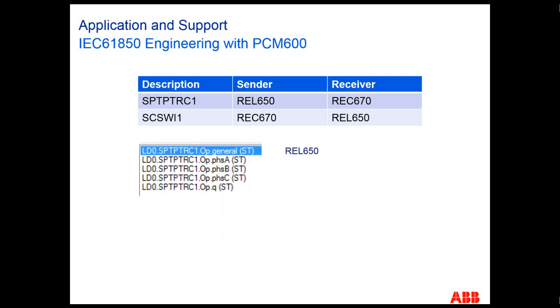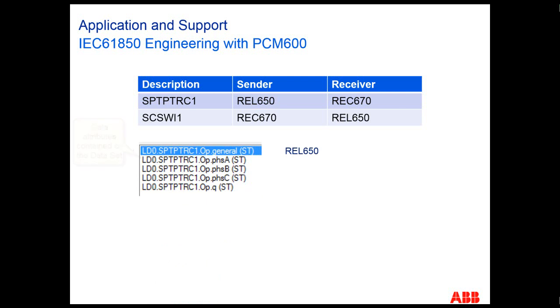These are the datasets that are going to be contained on the GOOSE message coming from the REL650 relay. We have a general operation, which is the equivalent of having any of the three-phase tripping — phase A, phase B, phase C — and the quality of the logical node.